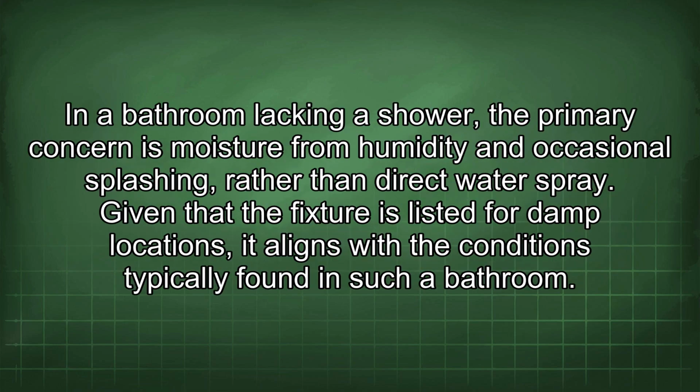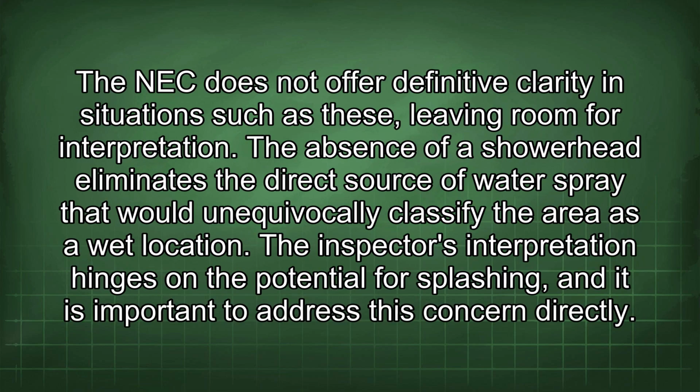In a bathroom lacking a shower, the primary concern is moisture from humidity and occasional splashing, rather than direct water spray. Given that the fixture is listed for damp locations, it aligns with the conditions typically found in such a bathroom. The NEC does not offer definitive clarity in situations such as these, leaving room for interpretation. The absence of a shower head eliminates the direct source of water spray that would unequivocally classify the area as a wet location.